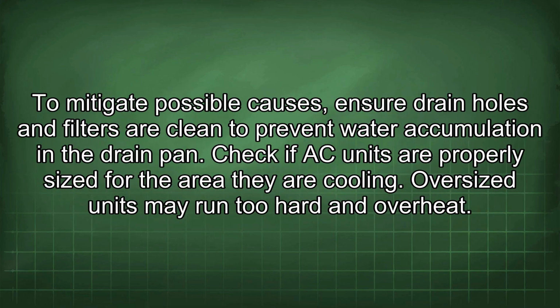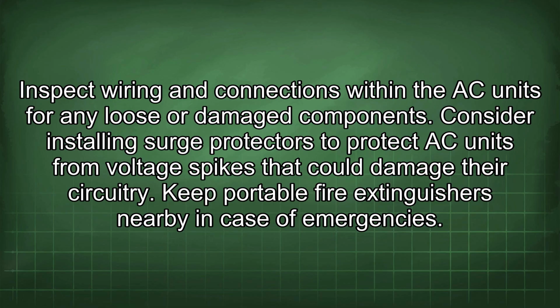To mitigate possible causes, ensure drain holes and filters are cleaned to prevent water accumulation in the drain pan. Check if AC units are properly sized for the area they are cooling. Oversized units may run too hard and overheat. Inspect wiring and connections within the AC units for any loose or damaged components. Consider installing surge protectors to protect AC units from voltage spikes that could damage their circuitry. Keep portable fire extinguishers nearby in case of emergencies.